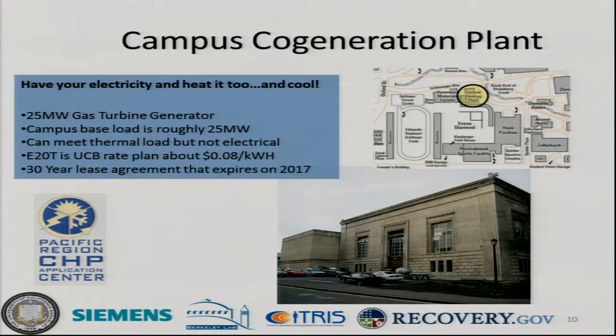The campus co-gen plant is located right off Evans Field by Haas Pavilion. It's a 16-megawatt gas turbine generator — the campus base load is roughly 25 megawatts, so we can't supply enough electricity to meet campus load, but we do have enough thermal load to meet a lot of campus heating needs. Because we have this co-gen plant on campus, we get a discounted rate on our electricity — the E20T rate, paying roughly $0.08 per kilowatt hour — due to our agreement with PG&E. In the summer, when we wouldn't use waste heat from the co-gen plant to heat buildings, we can use it to cool buildings like Sutardja Dai Hall that has the steam absorption chiller.